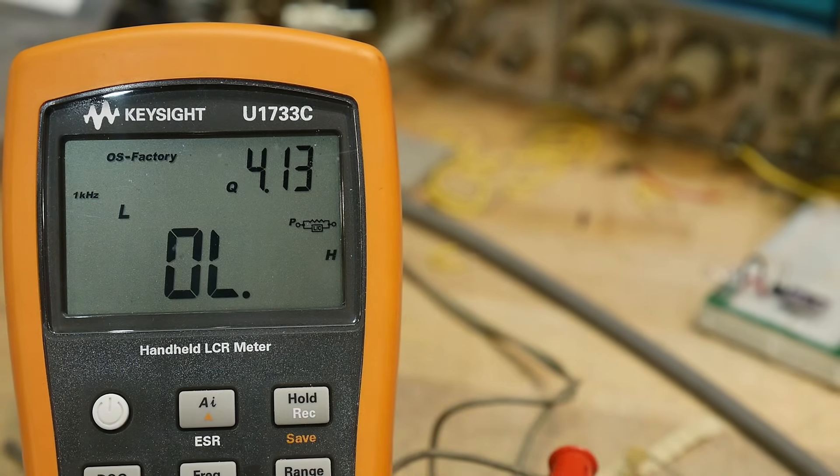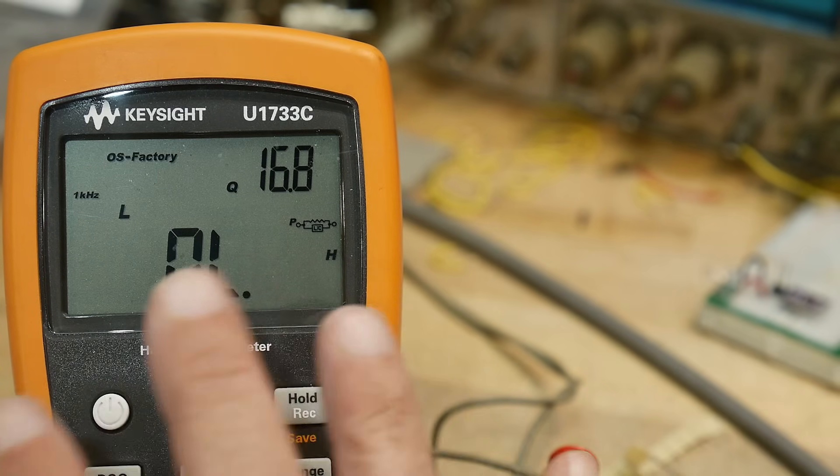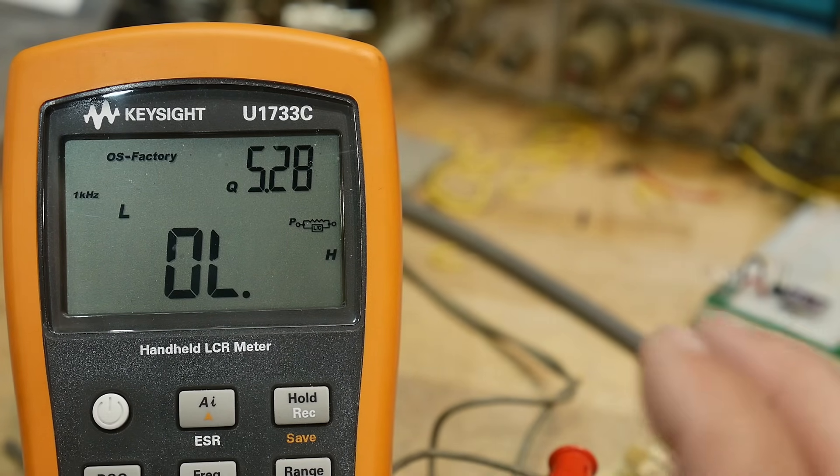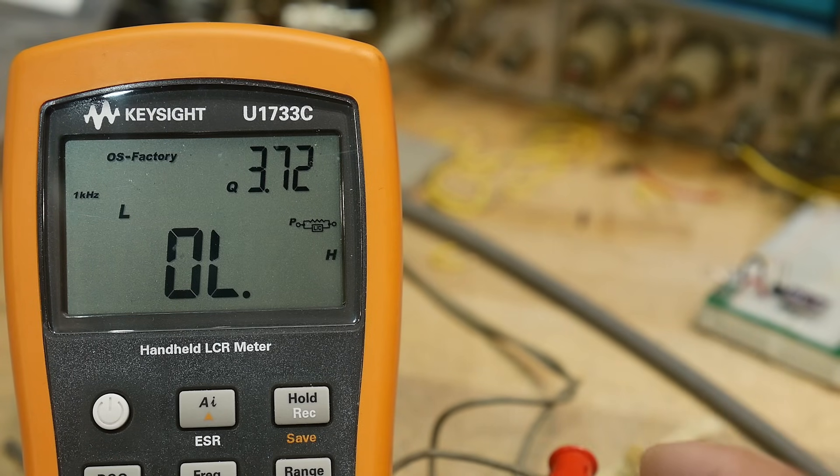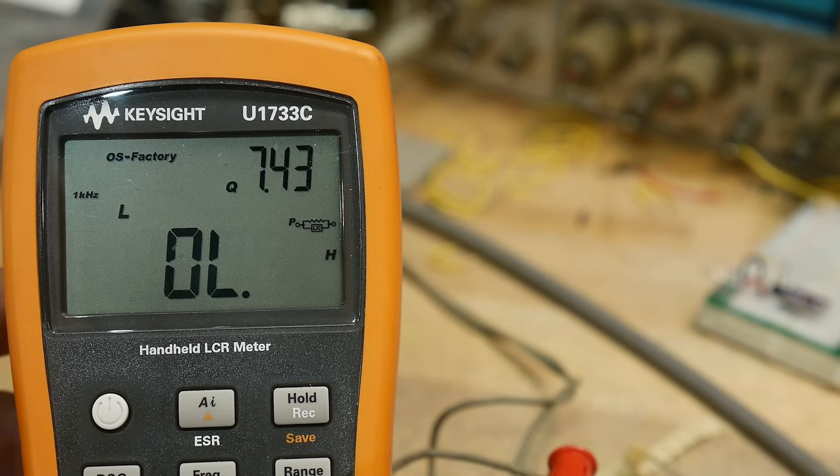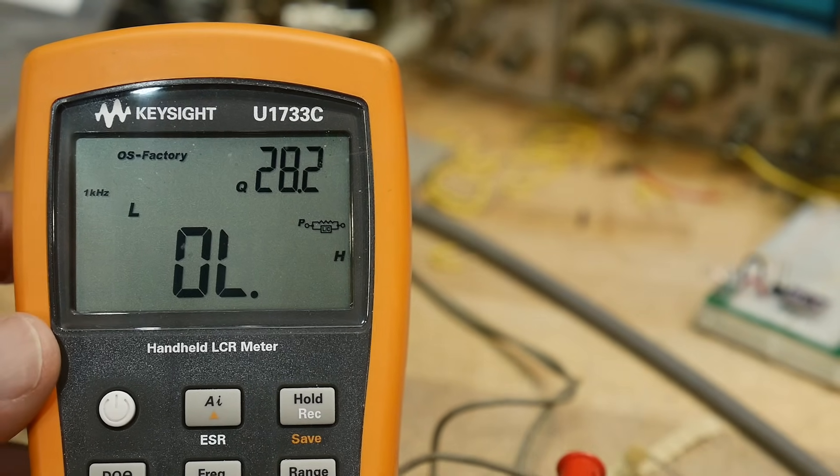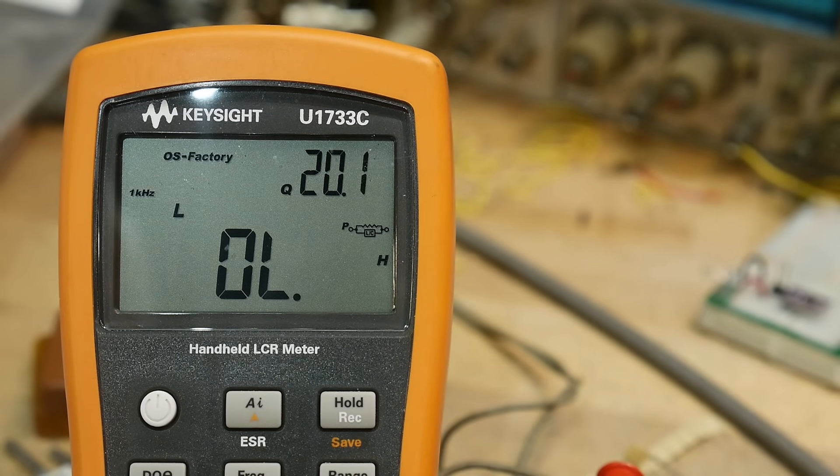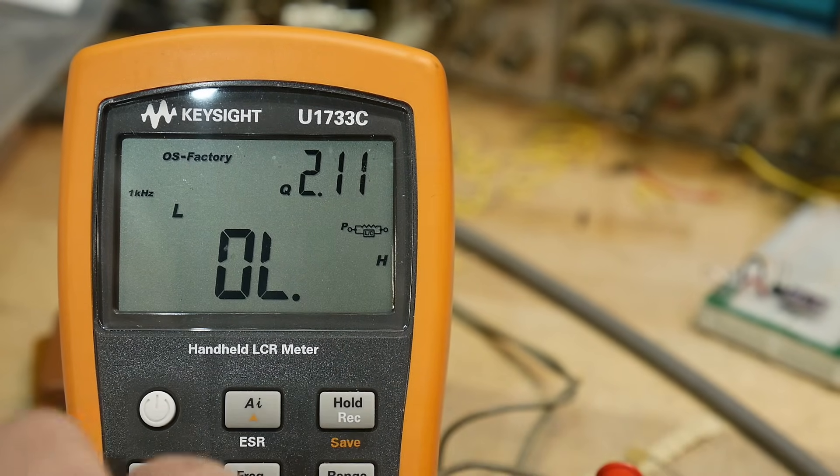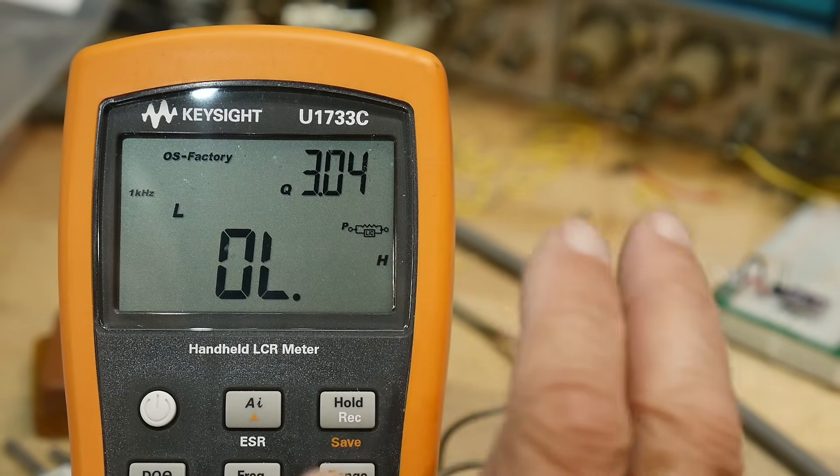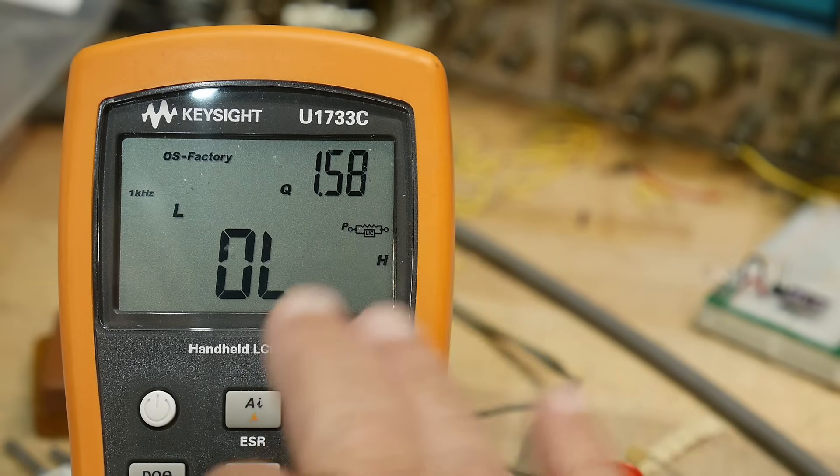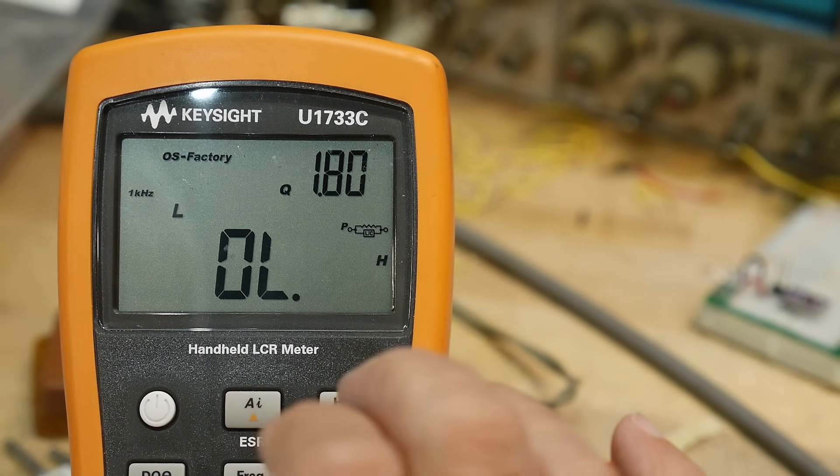And the question I get asked is, well, when do you use one over the other? Well, the meter chooses it for you. But assuming that you want to choose it yourself, why is one better than the other? And it comes down to impedance, effective resistance of the parts. And the rule of thumb is if it's below 100 ohms, either in resistance or reactance or whatever.